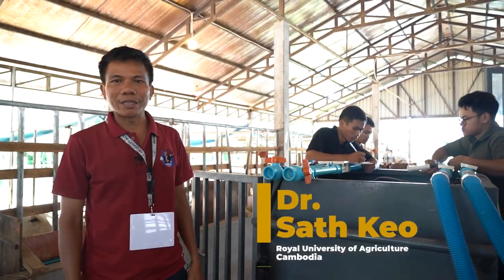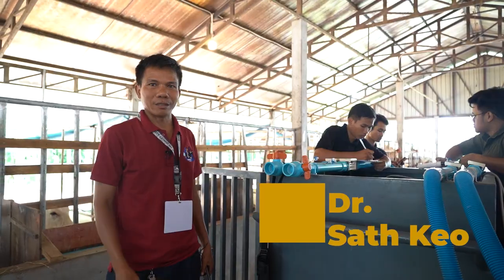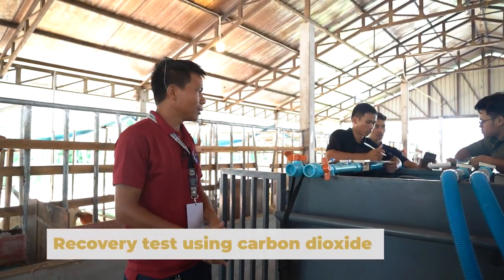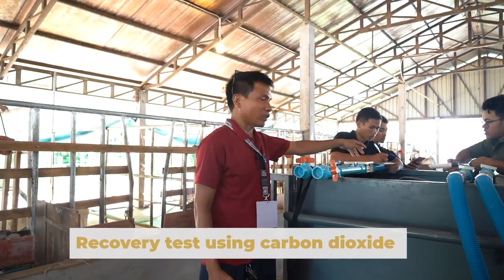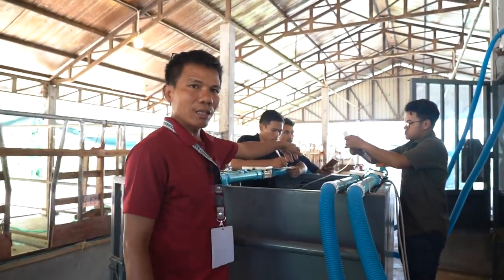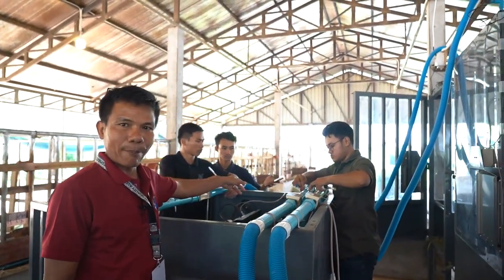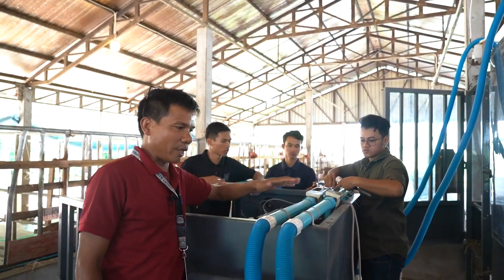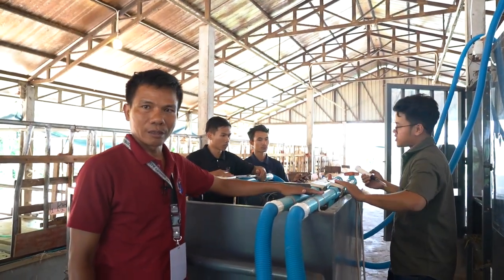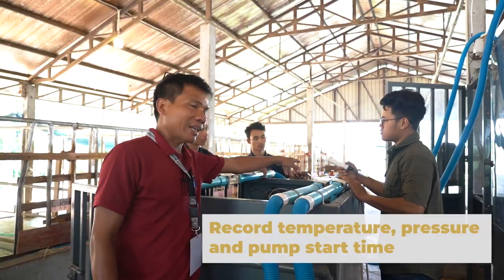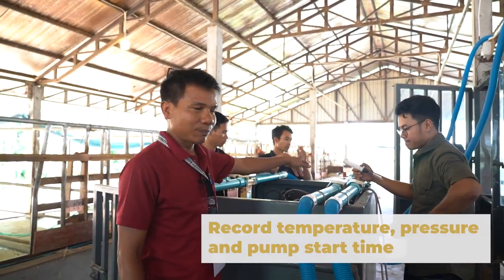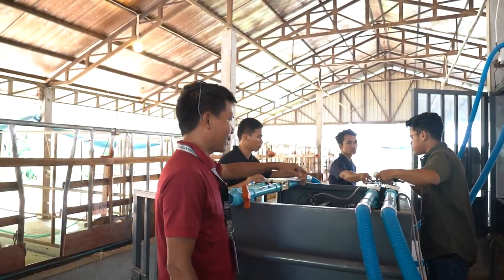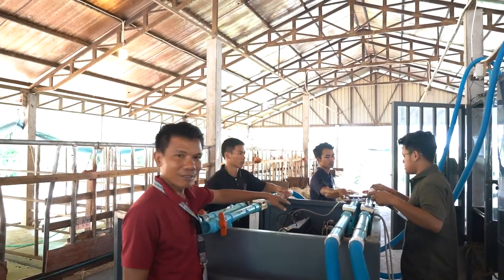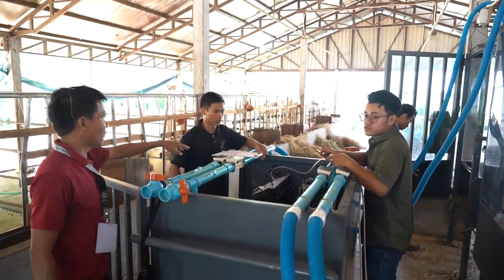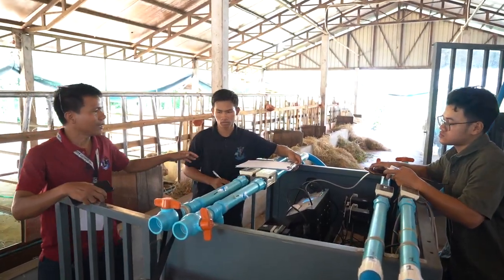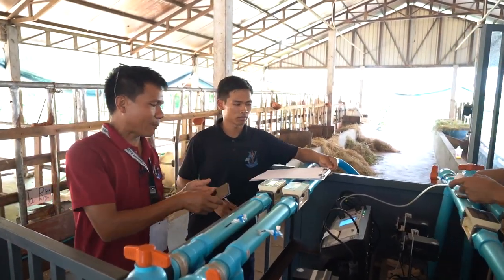Now we are doing the recovery test using CO2. Before we do that, we have to take the pressure and temperature through this equipment. For each box we have to write down the pressure and temperature. And we also start the time that the pump starts. My assistant here will record the time of start.